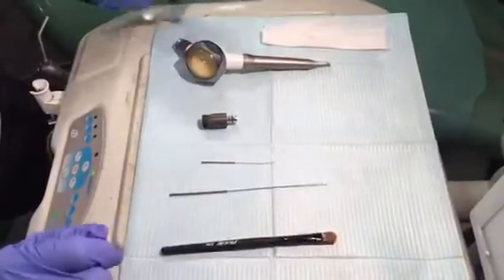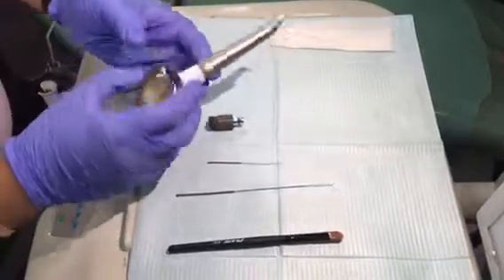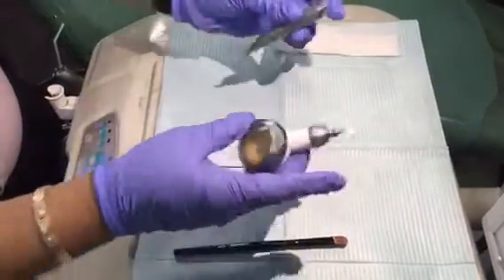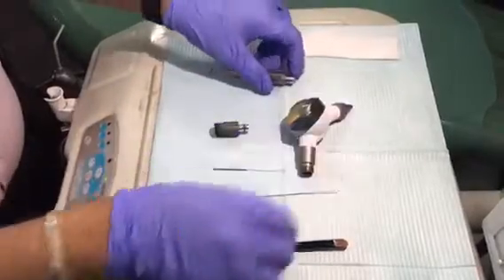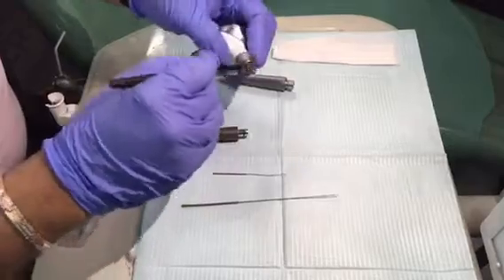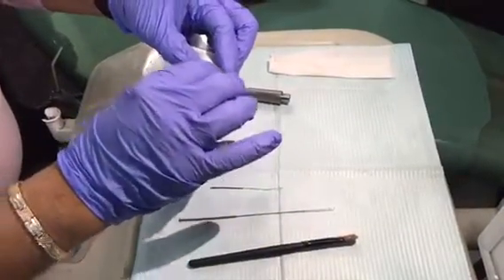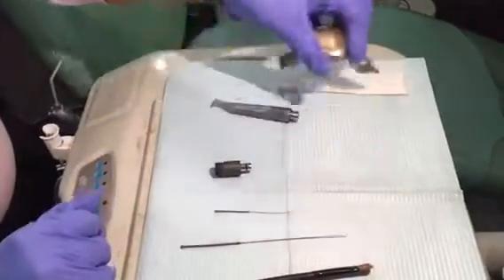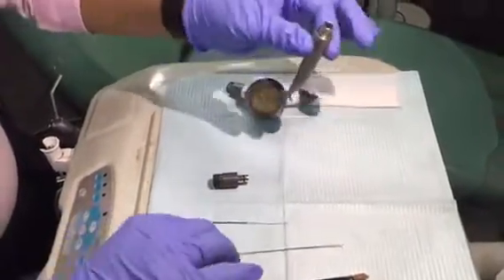This is all we get out of the box. This handpiece can be detached from the head. After you detach it, you need to clean all the powder contents from this area. After this is clean, in case you need, you can add a drop of oil here for lubrication.